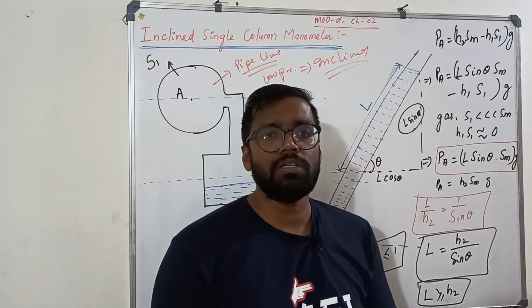So now please note down these 2 points. For the same pressure at point A, the reading in the inclined case will be more than the reading in your vertical case. And if the pressure at A is small, inclined single column manometers would be preferred. This equation 2 also shows that the inclined manometer is more sensitive compared to the vertical manometer. The sensitivity is more by 1 by sin theta times compared to the vertical manometer.